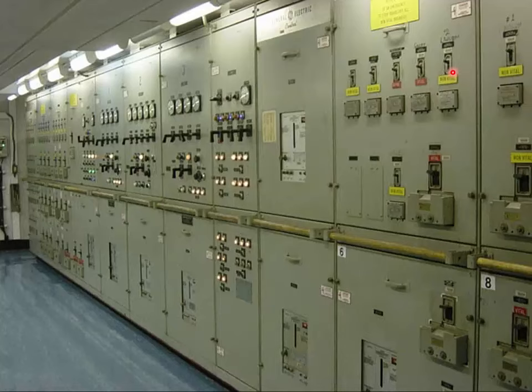And if you do that multiple times, not thinking, you can actually cause the circuit breaker to fault, and you can have a flashback or you can have a fire. So just be conscious of that. And then on our system on the Bear, not only do you have a circuit breaker, but you have a fuse block. Now, the circuit breakers are for normal overloads, these fuse blocks are for short circuits.